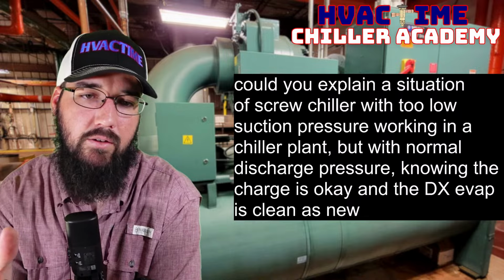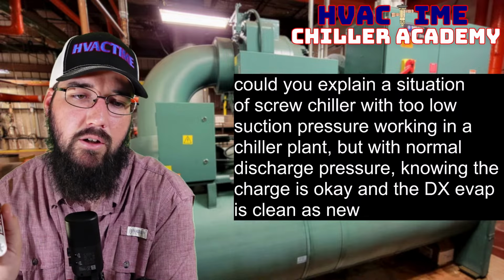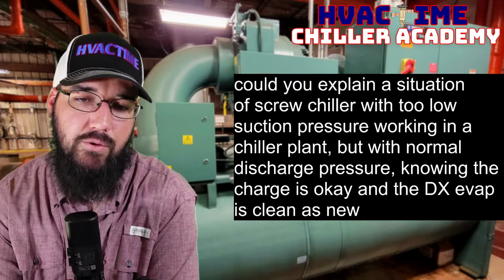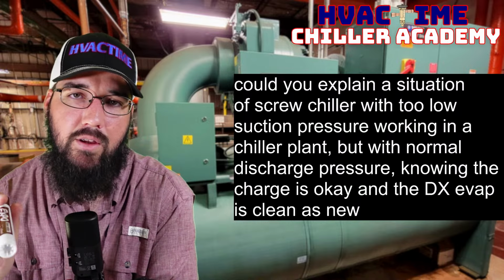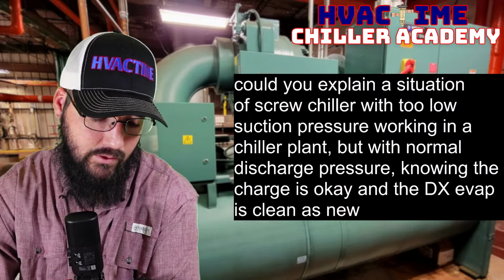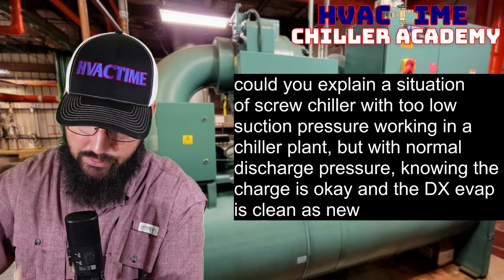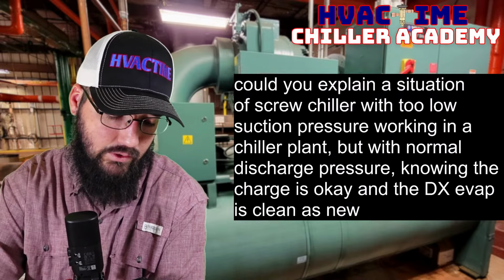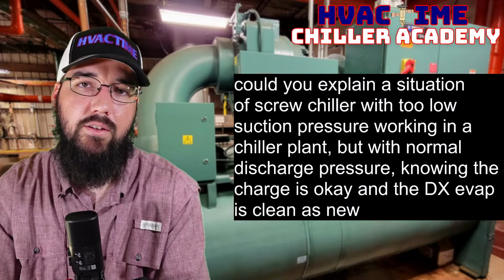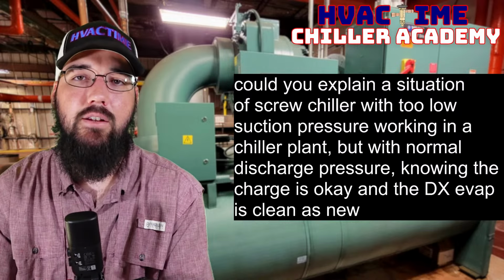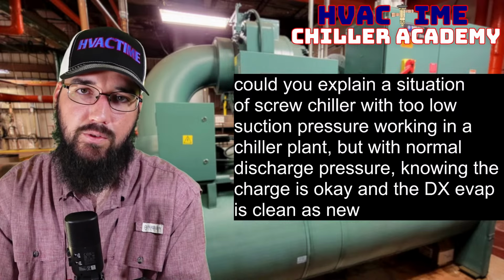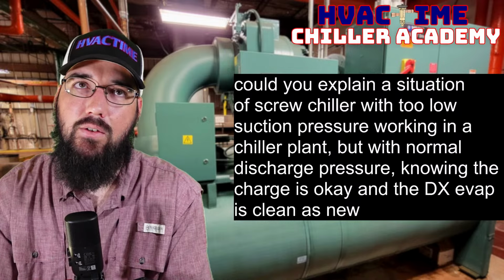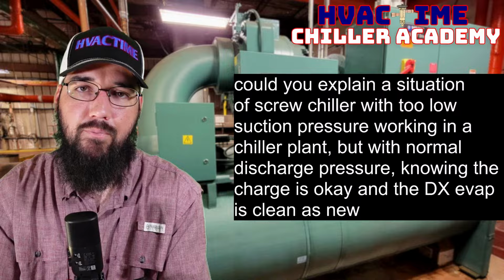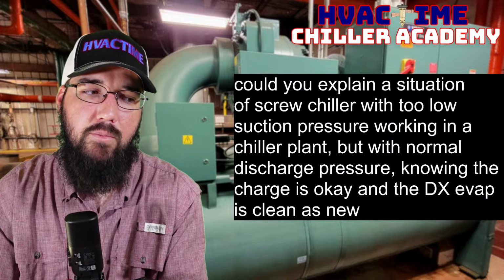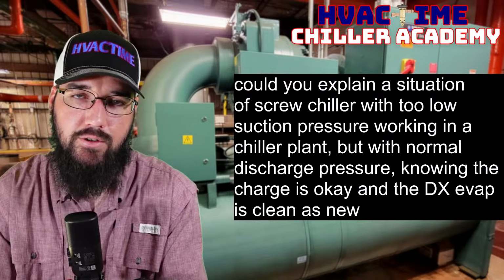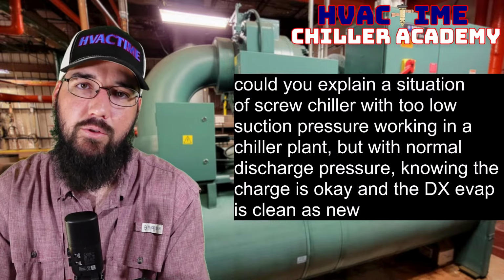So, explaining low suction pressure on a screw machine, but with normal discharge pressure. One of the things that I do want to point out in closing this, keep in mind the discharge pressure is going to be relative to the ambient conditions, especially with an air-cooled system specifically. So if you've got a higher ambient, just because you've got low suction pressure doesn't mean that you are automatically going to have really low discharge pressure.